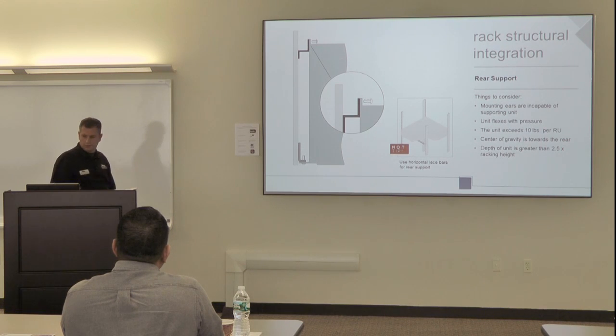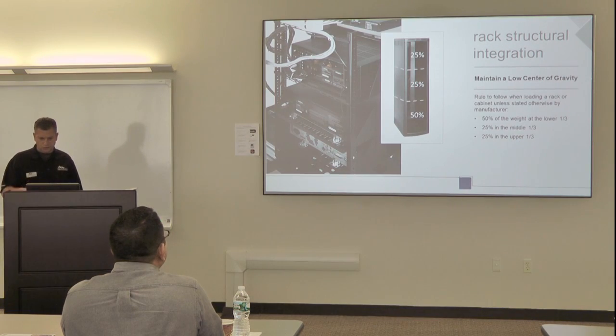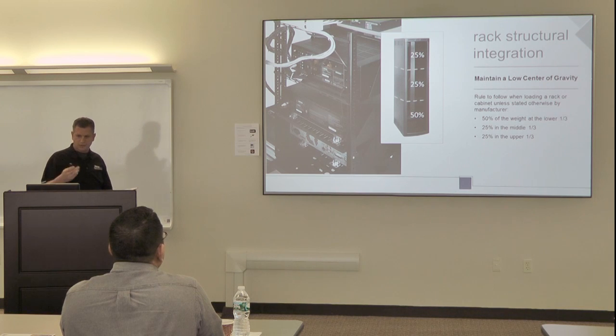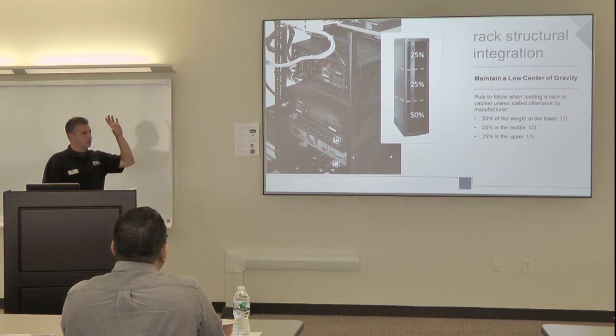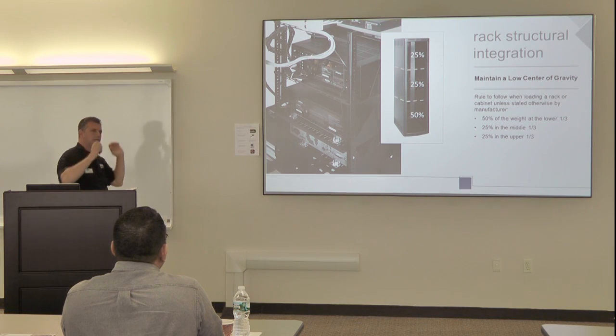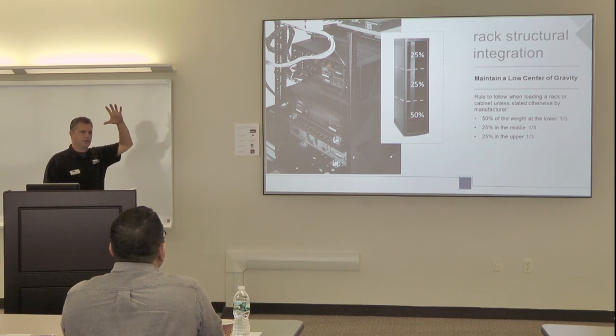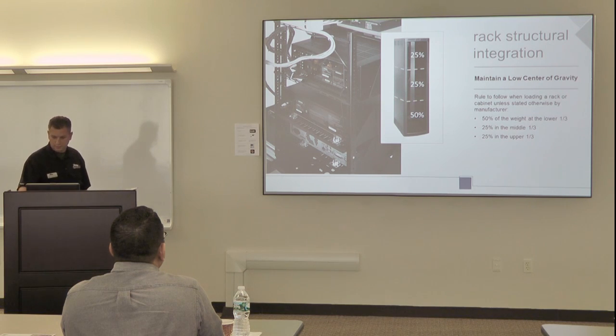We touched on this already: a key rule is 50% of the weight in the bottom third, then 25% and 25% above, and again we test to that standard. If the rack is on casters, you often want to push from up high to avoid tipping. Part of the test is actually tilting it 10 degrees with that weight loaded, to make sure it won't tip over and hurt anybody.